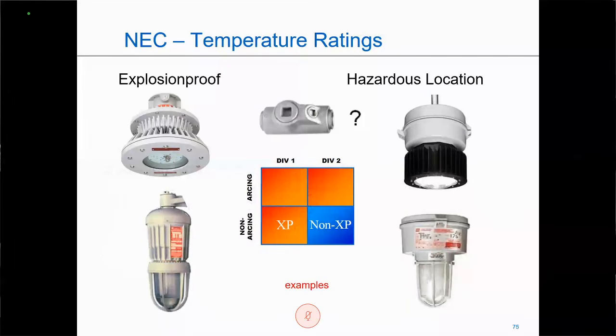Now, another question comes up: do I need to seal these particular luminaires? Well, if we think back to my 4 square, these are not arcing sources. They're really glorified junction boxes. Now, yes, they have the socket wired inside. If it's an HID, they have the ballast wired inside. But really, they are glorified junction boxes that happen to have a lens where the light can exit. You know, it's going to have a driver if it's an LED.